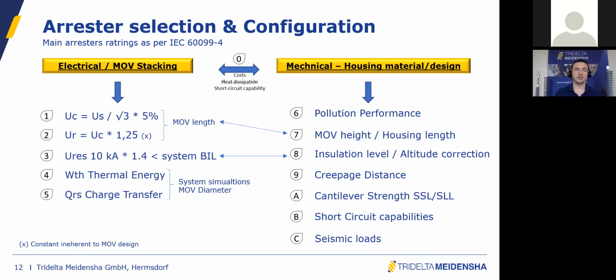Now if we go to the electrical configuration, the idea is to find the right arrangement of MOV stacking. If you look at the camera, what we call the MOV, the metal oxide varistors, or those blocks, looks pretty simple. I'm sure that most of you are familiar with that. We are playing with those blocks to reach the electrical requirements. So basically, if we talk about the rated voltage or the continuous operating voltage, we are going to play with the number of blocks.